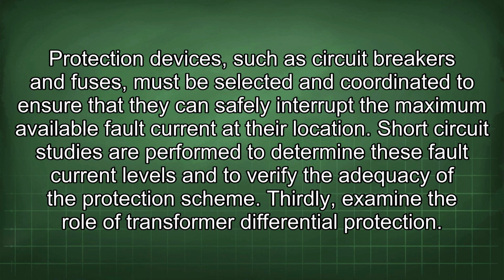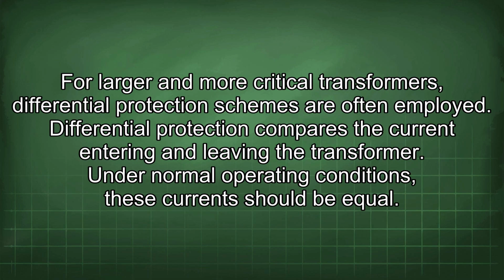Thirdly, examine the role of transformer differential protection. For larger and more critical transformers, differential protection schemes are often employed. Differential protection compares the current entering and leaving the transformer. Under normal operating conditions, these currents should be equal.